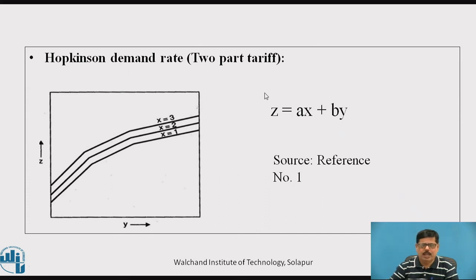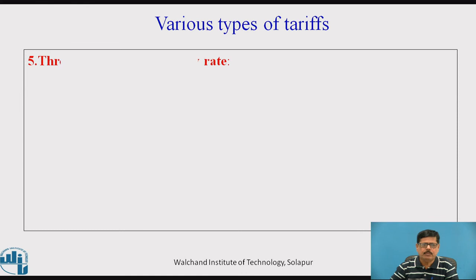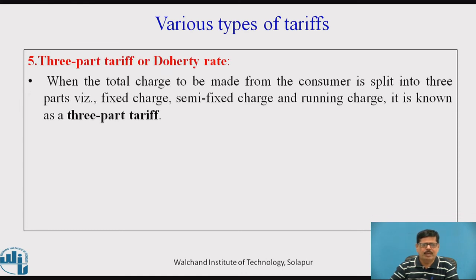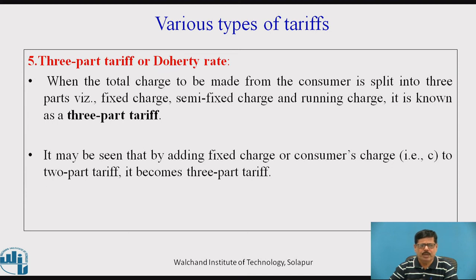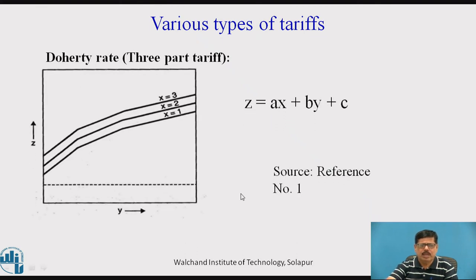The last method is the three-part tariff or Doherty tariff. When the total charge is split into three parts — fixed charge, semi-fixed charge, and running charge — it is known as three-part tariff. It is a modified form of the Hopkinson two-part tariff: by adding a fixed consumer charge C, the two-part tariff becomes the three-part tariff, given by Z = AX + BY + C. This type of tariff is generally used for big consumers.